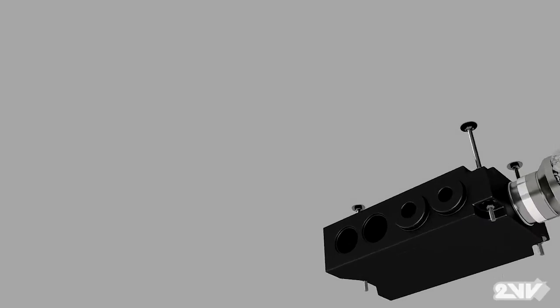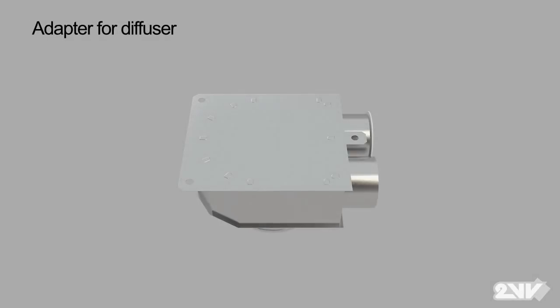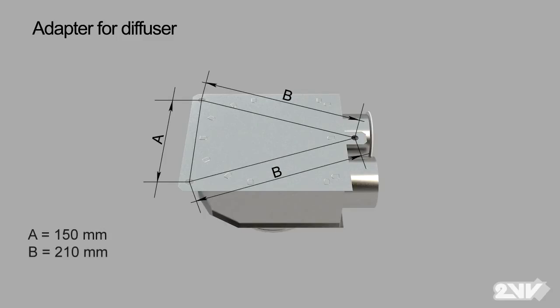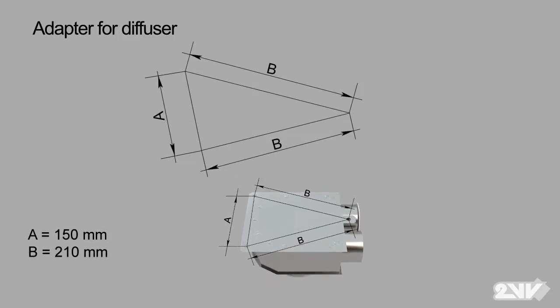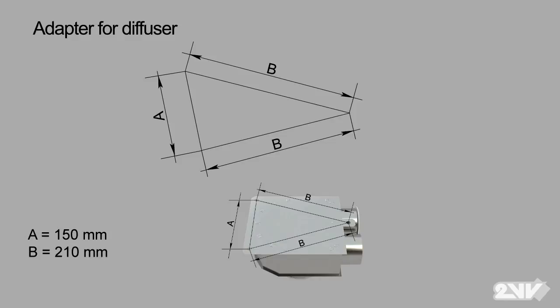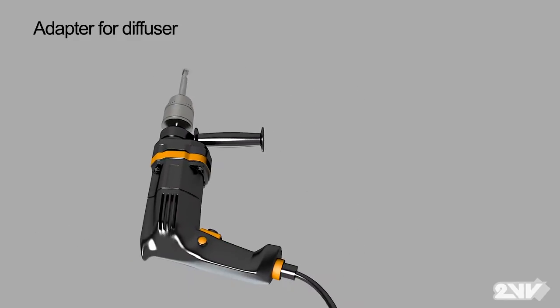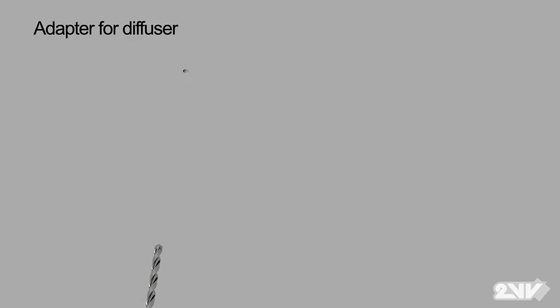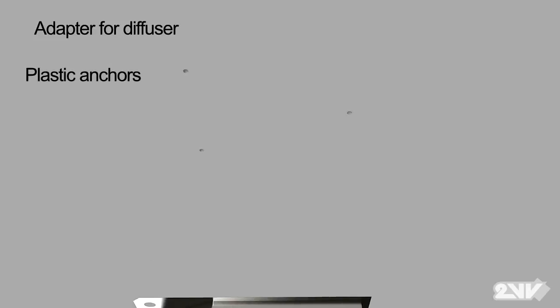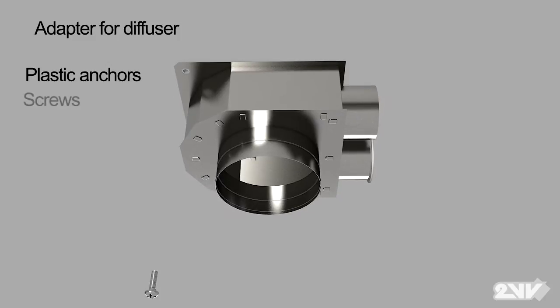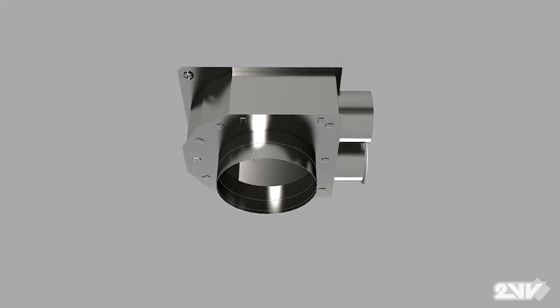Now it's time to install the supply diffusers to the ceiling. Taking the diffuser, mark holes in the ceiling in the same way as before. Drill 3 holes according to marks on the ceiling. Here you will need anchors and screws. Secure the diffuser to the ceiling.